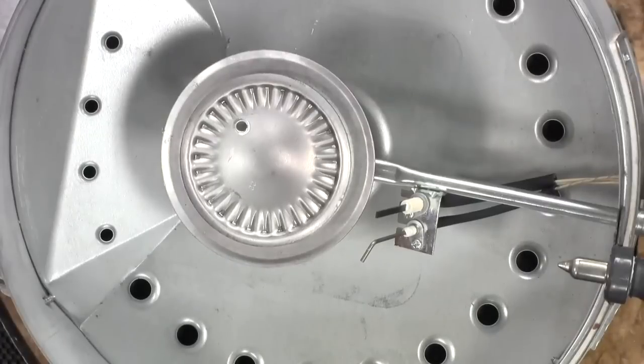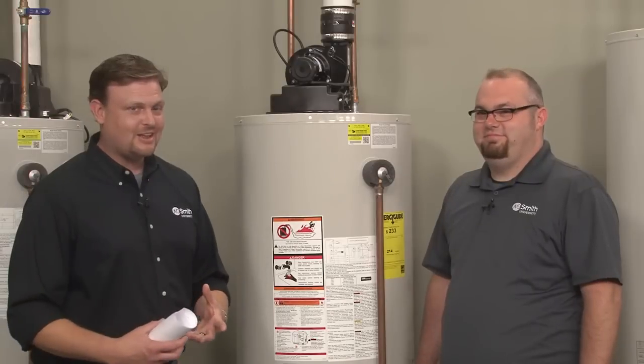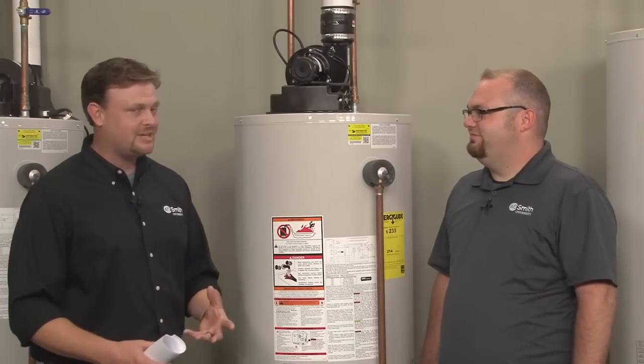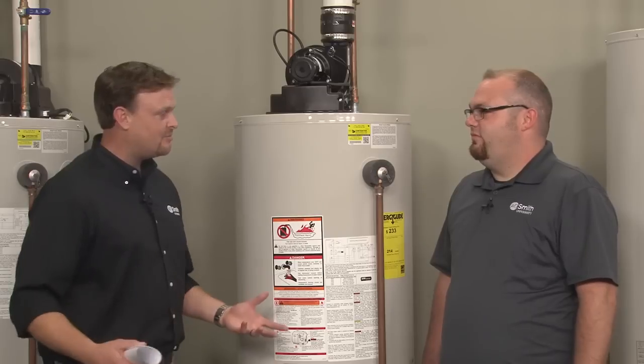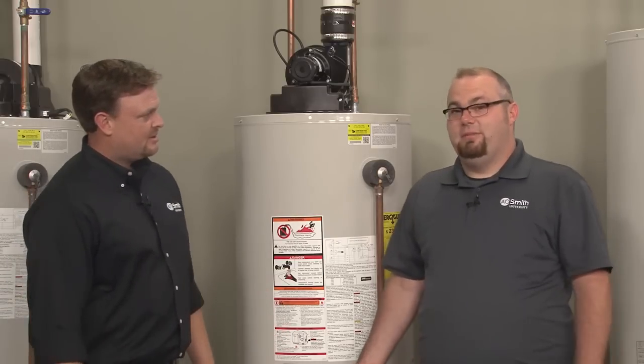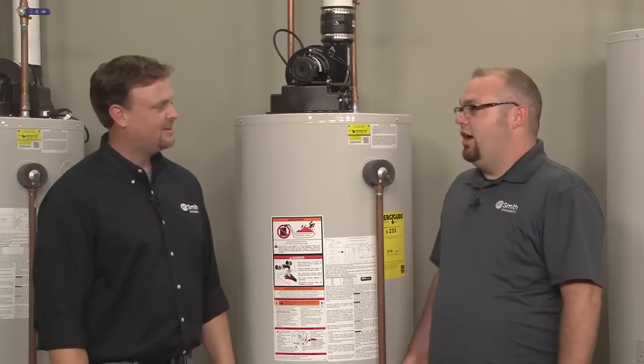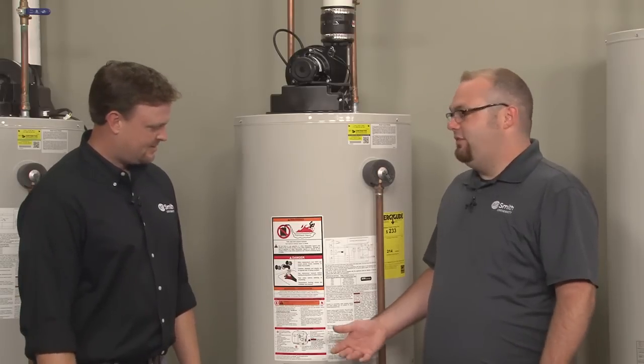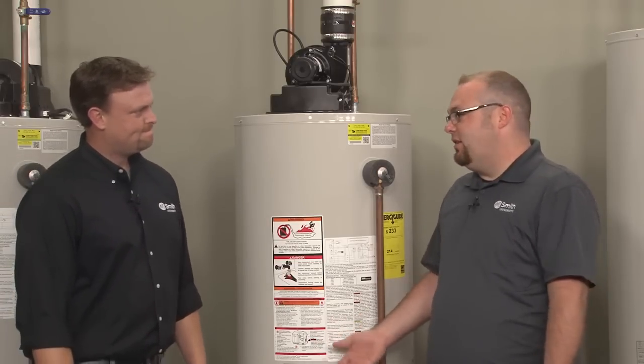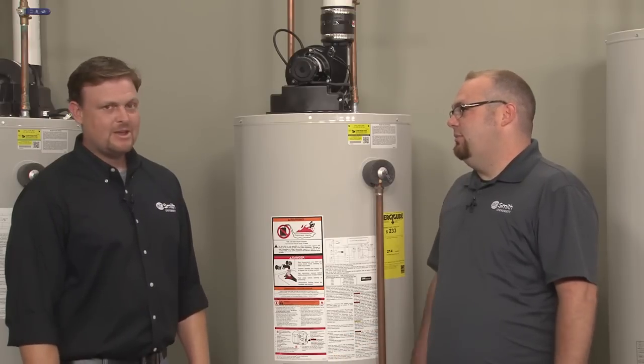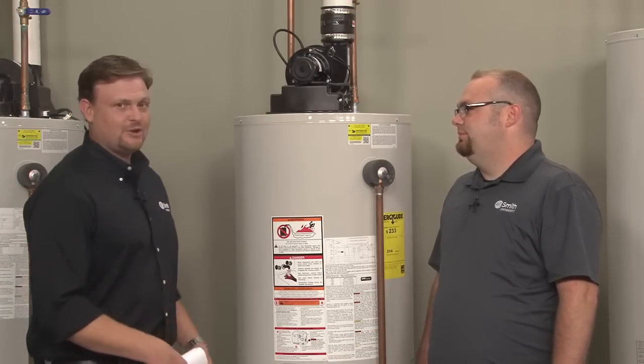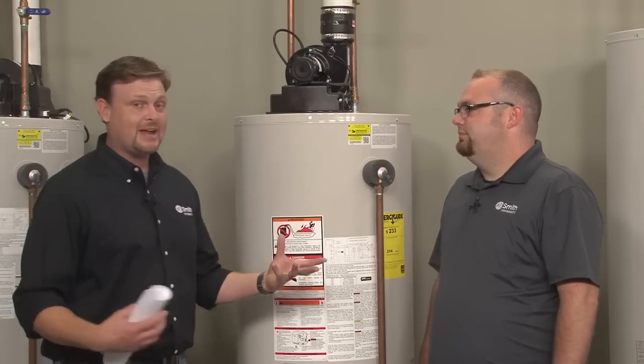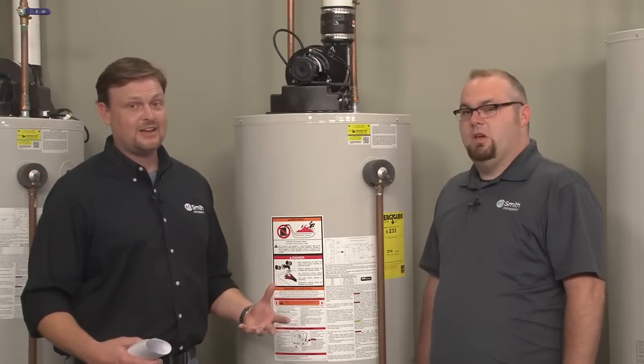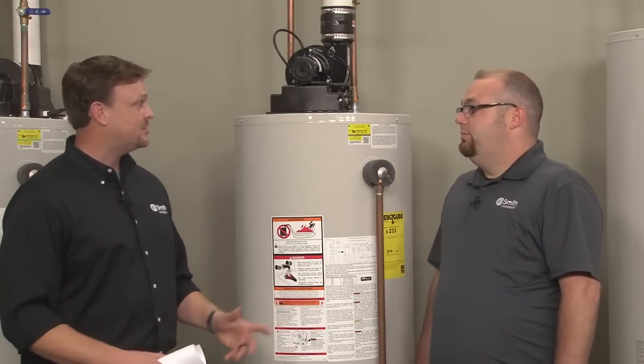All right. What if I walk up to it and I don't see a flame? It tries to light, we see the glow for 17 seconds, and then it just goes out. I never do see a flame. If you don't see a flame, then I'm usually going to go down the gas road. It could be several different things, but typically it's going to be gas coming to the heater. Just check to see if you have gas coming to it. Yeah, and that could be closed valves upstream. It could be air in the gas line, because that's one thing that happens on new installs, is you might have a pocket of air in that gas line. So you're going to need to bleed that air out to be able to get it to fire.